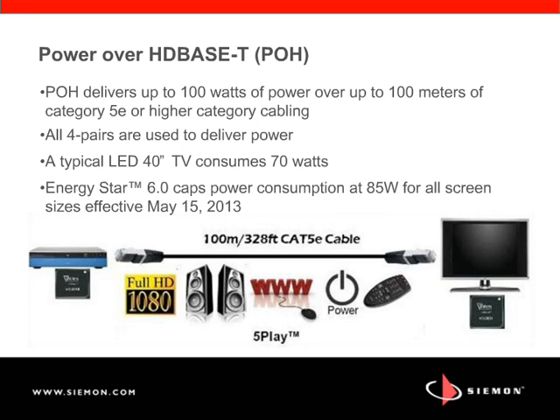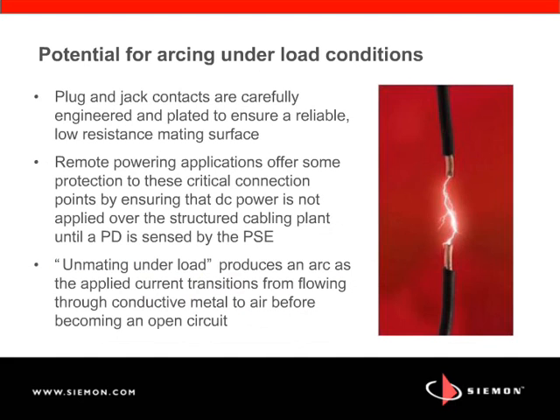Now, there are ramifications and implications, both electrical and mechanical, for applying these types of power levels over structured cabling. Now, the first is what happens when I break connections when DC power is appearing across the conductors in a twisted pair circuit. Telecommunications modular plug-and-jack contacts are very carefully engineered, and they're plated typically with gold or palladium to ensure a reliable, low-resistance mating surface. Today's remote powering applications, specifically Power over Ethernet applications, offer some protection to these connection points by ensuring that DC power is not applied over the structured cabling plant until a powered device is sensed by the power sourcing equipment.